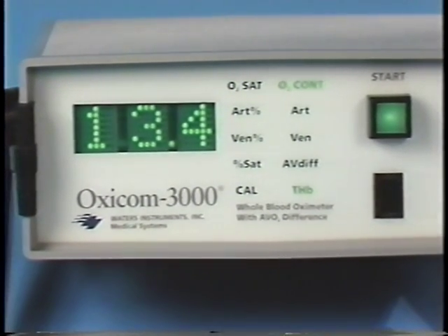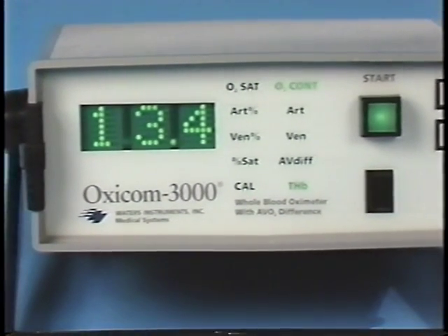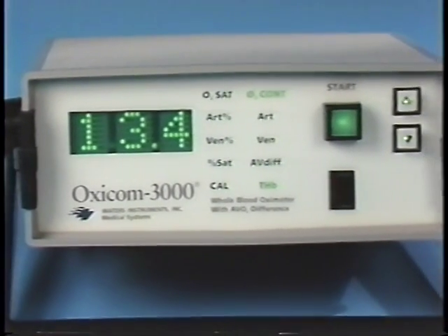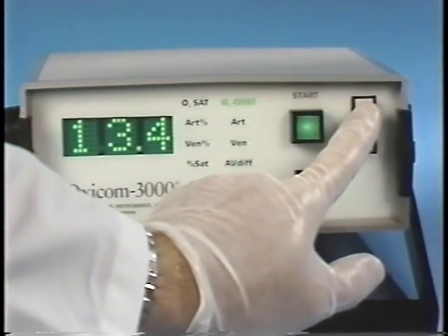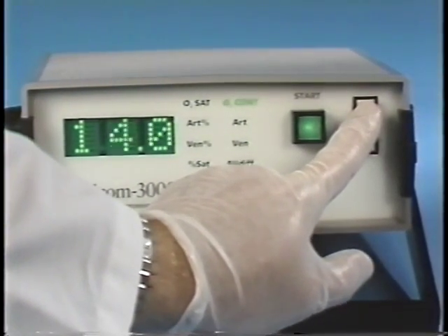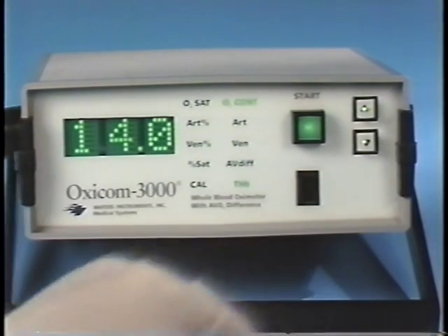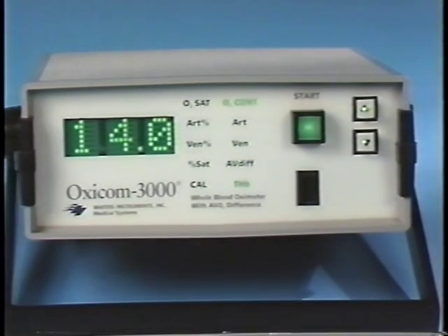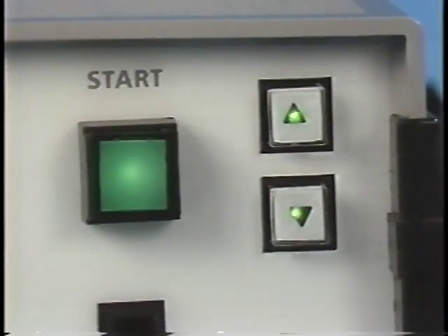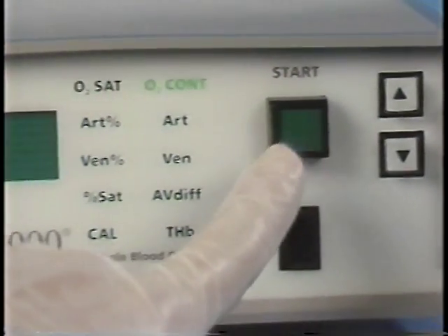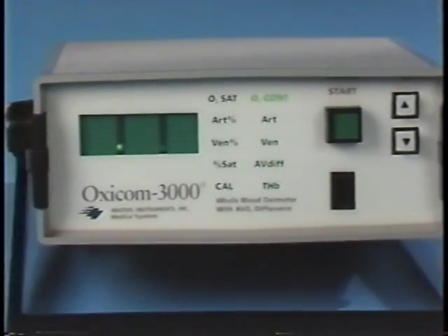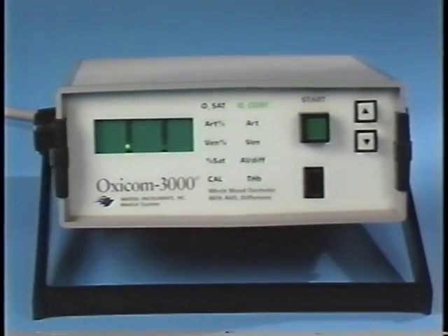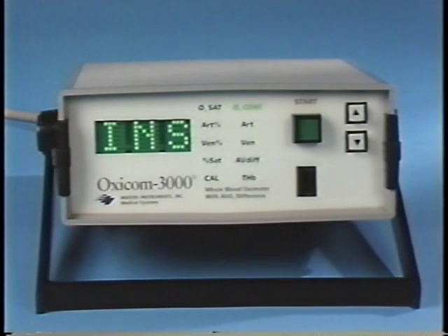Enter your patient's hemoglobin value by pressing the up or down arrows to the right of the start button. If your value is higher, press the up arrow until the correct value is displayed. If lower, press the down arrow. After the correct hemoglobin value is displayed, press the start button to lock the hemoglobin value into memory. That value will then be used for all future content calculations until changed. The display will clear and then show INS.